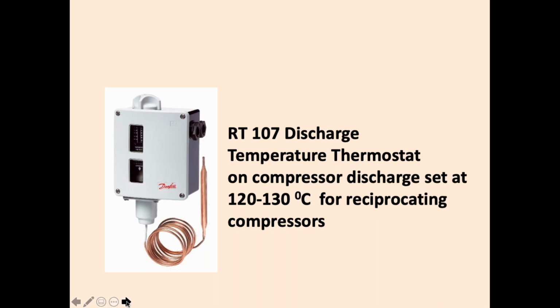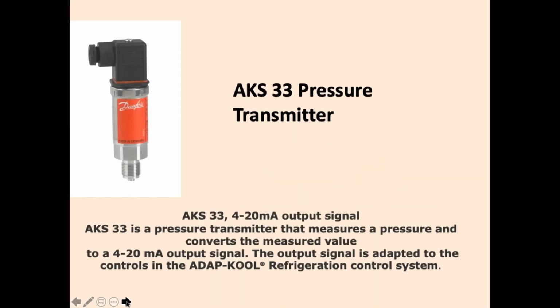If the compressor discharge temperature is going up for any reason, like valve plate breakage or any other reason, or the discharge pressure is going up and the temperature is going up, the temperature switch will trip the compressor and protect it instead of creating a problem. So for the high discharge temperature switch, for mineral oils around 130 degrees centigrade is good enough. These are the pressure transmitters. These are for automatic plants. You can use pressure transmitters.